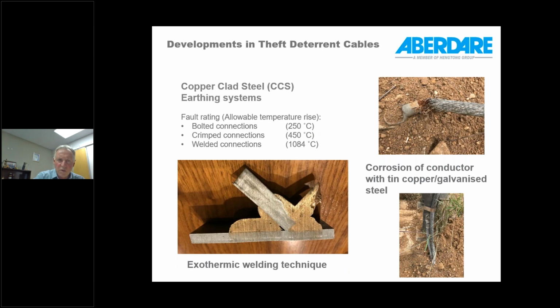So one would need to consider this when applying these conductors, that if such an earth conductor is right next to another cable, like in this picture for instance, having this conductor go up to 1,000 degrees is not going to be very good for the cable that it's installed next to. And of course, as we spoke earlier, bimetallic corrosion is a problem with these type of conductors as well, when you're talking about bimetallics. But for copper-clad steel, corrosion is not an issue. It's recommended that the ends are protected where the steel is exposed, and that a type of lug that doesn't allow water to enter is used, and anti-oxide paste is used when you're terminating these type of conductors.